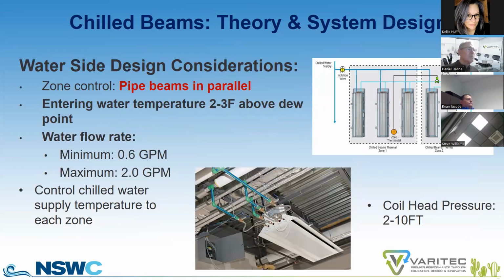How are chill beams to be piped? Well, they need to be piped in parallel. We don't want to pipe them in series. There was a design in Flagstaff that was, to my understanding, really inhibited consideration of chill beams in the future. The engineering team laid out the beams in series. You did not have the stated performance in the beams further down the line in that piping series. Consequently, the room energy levels were never satisfactorily met.